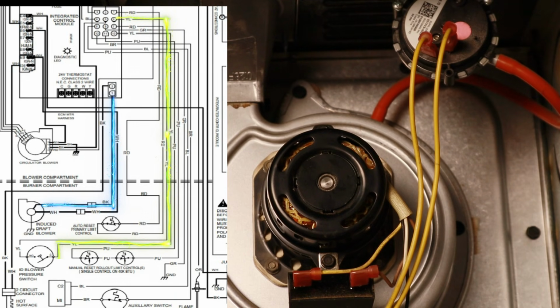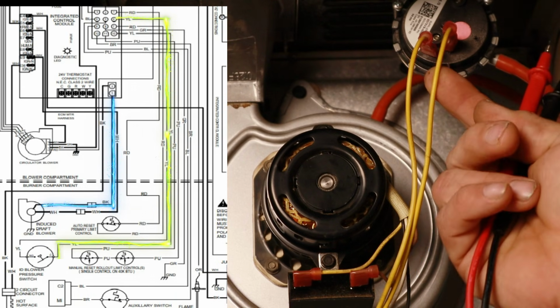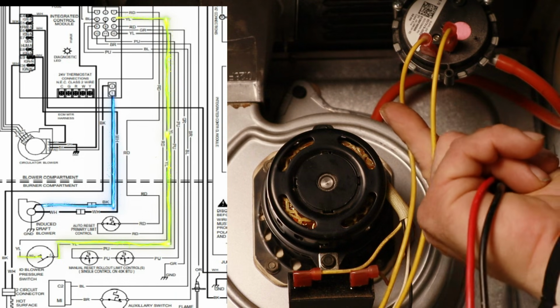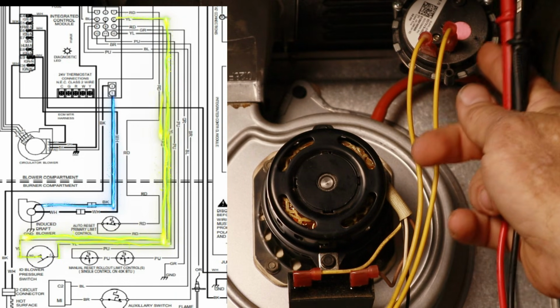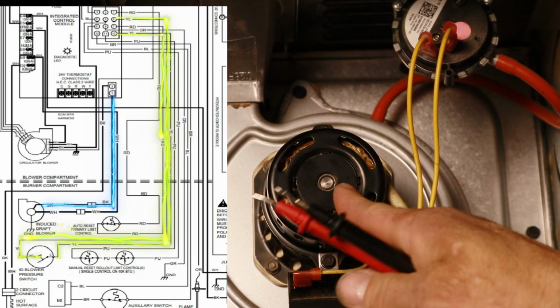So we can see here on the schematic we have the inducer draft blower pressure switch. All right, and we can see that there's two yellow wires, one feeding in, one coming out. So during the startup sequence, we should have 24 volts coming from our control module off of that Molex plug, going into our blower switch here, and then 24 volts coming out the other side, so long as this switch is closed when this inducer motor is running.